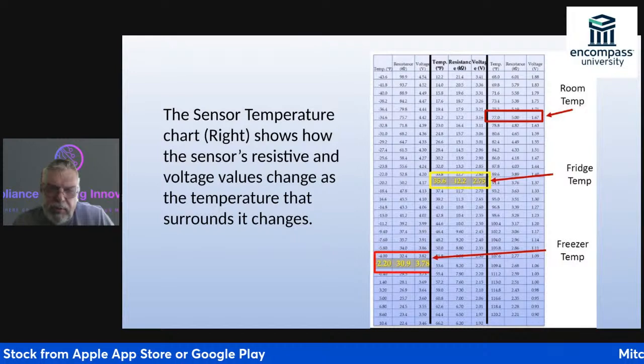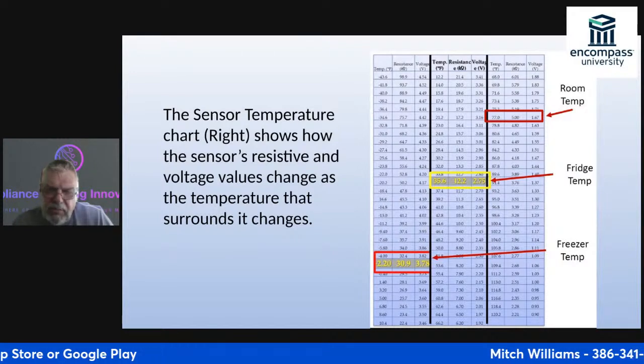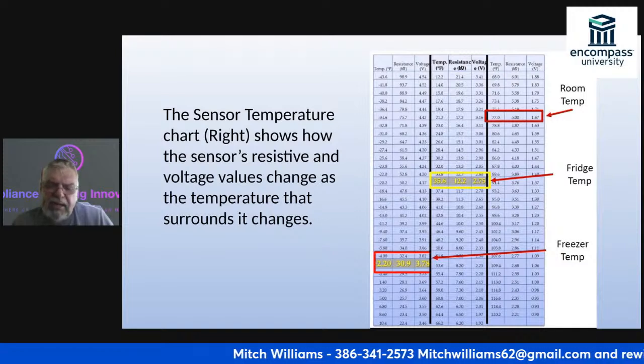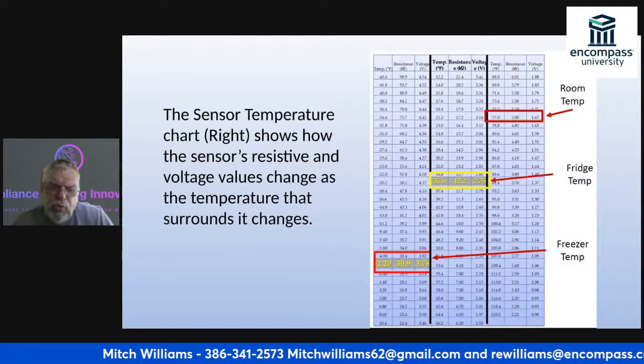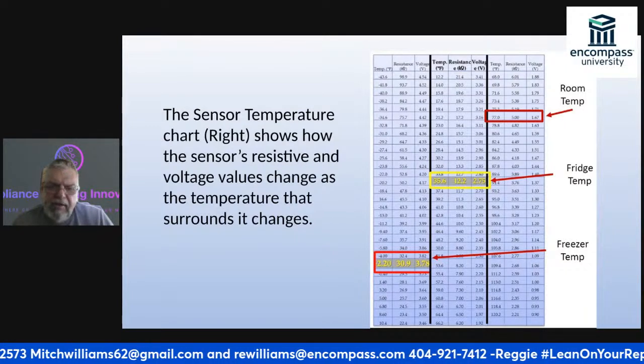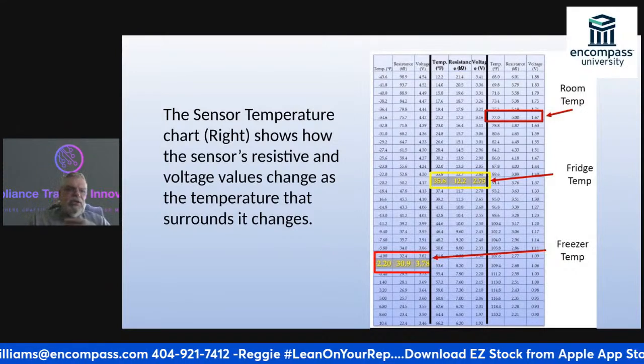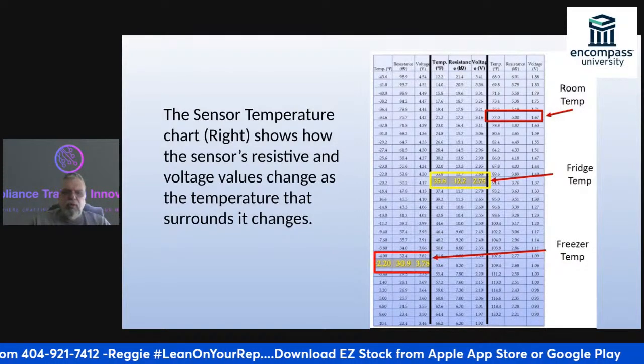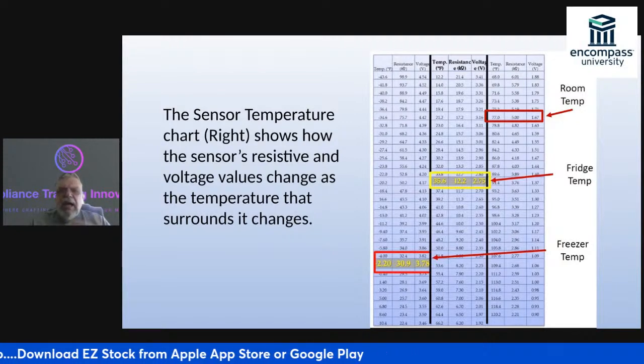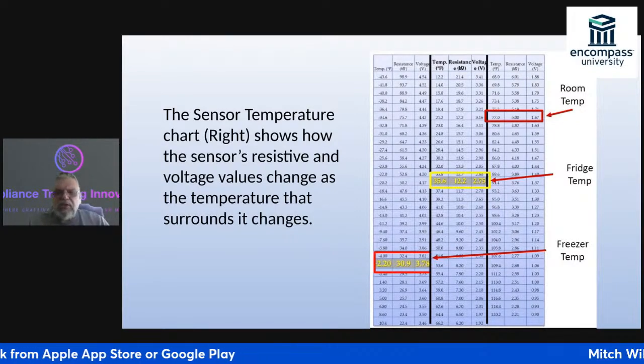Most people's refrigerator is usually set somewhere around 0 to -4. So if you look at -4, I now have 32.4 ohms, or I'm going to have about 3.82 volts. So you need to remember this as you're going through. The sensor tells you right there, as the temperature decreases, my resistance goes up.